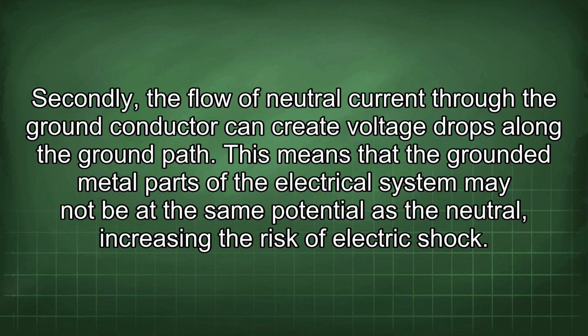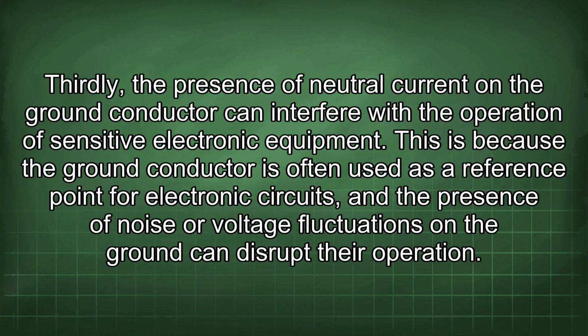Secondly, the flow of neutral current through the ground conductor can create voltage drops along the ground path. This means that the grounded metal parts of the electrical system may not be at the same potential as the neutral, increasing the risk of electric shock. Thirdly, the presence of neutral current on the ground conductor can interfere with the operation of sensitive electronic equipment. This is because the ground conductor is often used as a reference point for electronic circuits, and the presence of noise or voltage fluctuations on the ground can disrupt their operation.